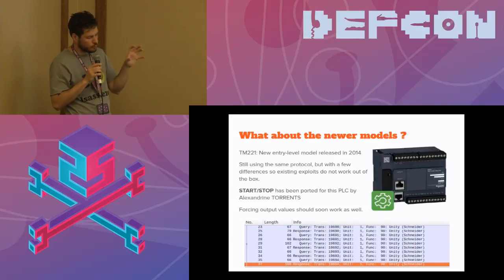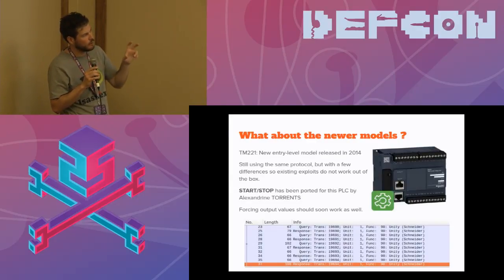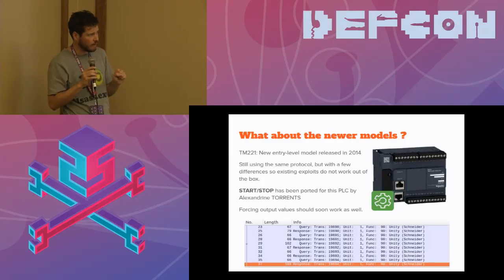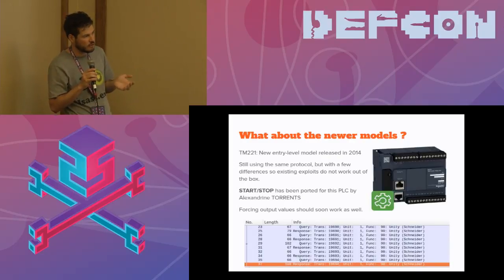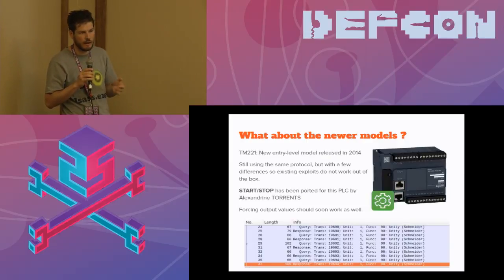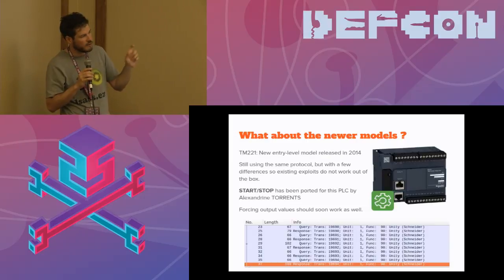That was true for the Premium, Quantum, and M340 PLCs. What about the newer ones? In 2015 I bought the newly released TM221 — entry-level PLCs. What I discovered is that even though they're not programmed by Unity Pro but by another software called SoMachine Basic, they still use the same function code. So even PLCs released two years ago, despite the known lack of authentication on admin actions for almost ten years, still have the same problem. The exploits don't work out of the box — you have to change some offsets — so it's vulnerable but you can't exploit it directly yet. My colleague Alexandrine has already contributed modifications to the Metasploit module, so you can now start and stop those devices without any authentication directly from Metasploit.